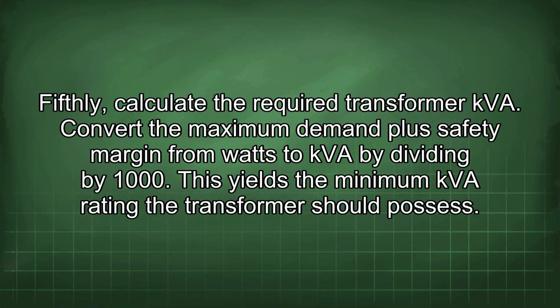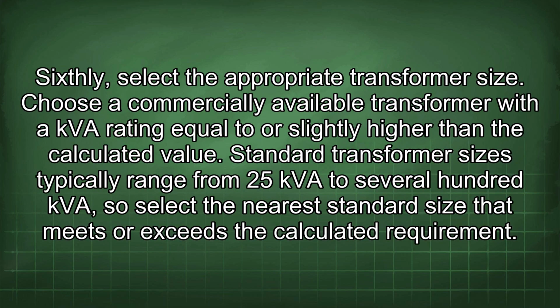Fifthly, calculate the required transformer kVA. Convert the maximum demand plus safety margin from watts to kVA by dividing by 1000. This yields the minimum kVA rating the transformer should possess. Sixthly, select the appropriate transformer size. Choose a commercially available transformer with a kVA rating equal to or slightly higher than the calculated value. Standard transformer sizes typically range from 25 kVA to several hundred kVA, so select the nearest standard size that meets or exceeds the calculated requirement.